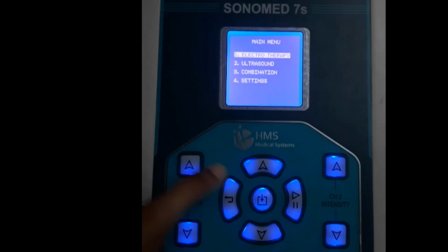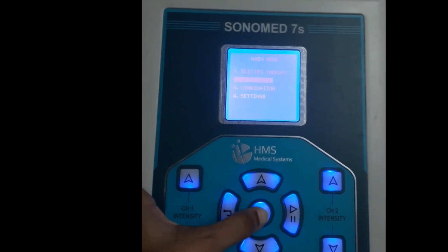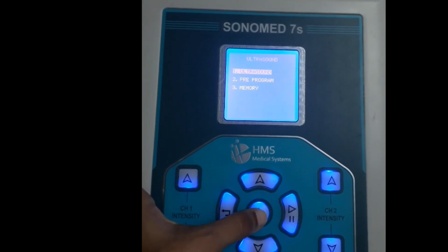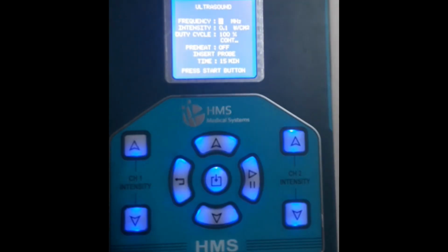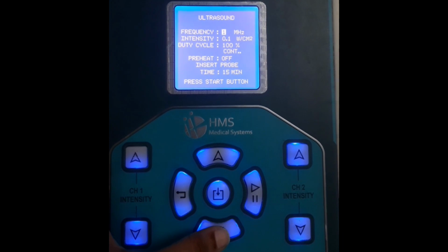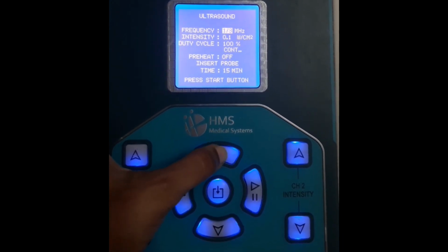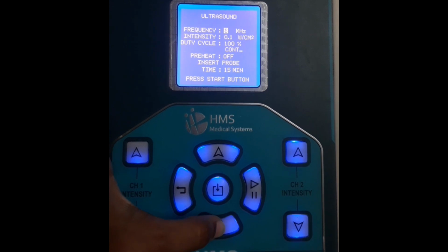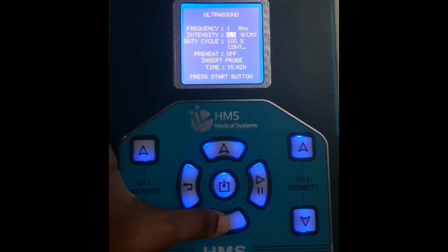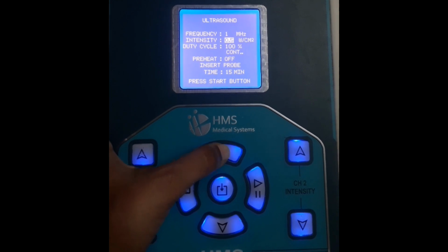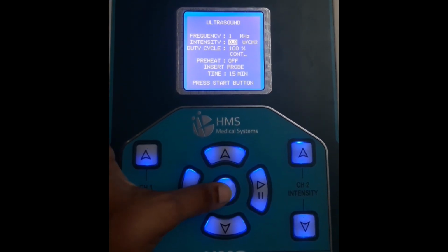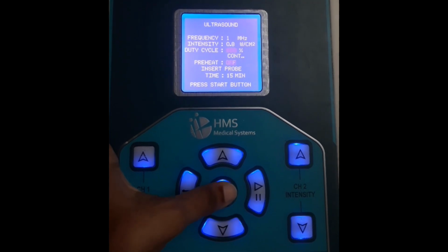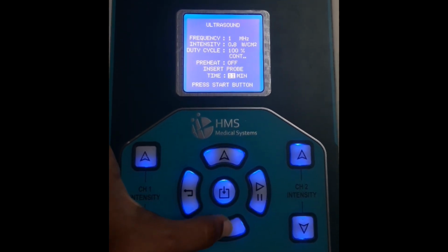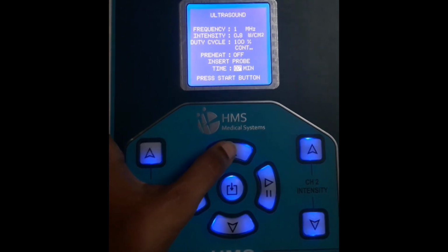Turn on the switch. Select ultrasound. Set the frequency to 1 MHz. Set the intensity to 0.8. Duty cycle 100%. Preheat is off and the timer is set to 8 minutes.